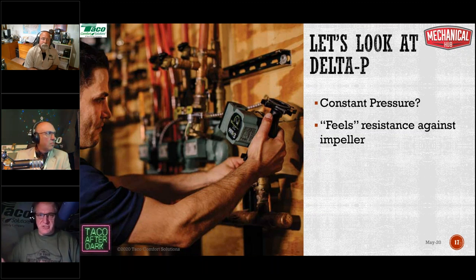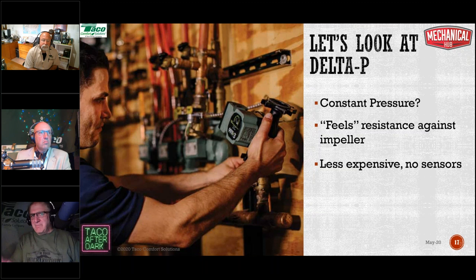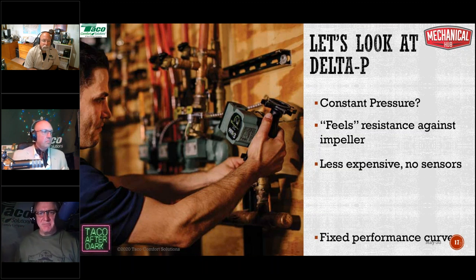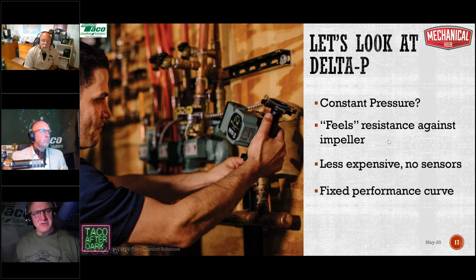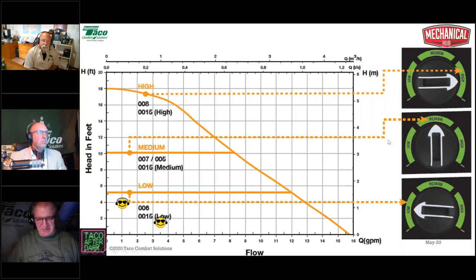Another zone closes, more resistance, and we slow down again. A zone opens, less resistance, something's changed, so I must go faster to maintain my 10 feet of head constant pressure differential. That's how it works under constant pressure, which is the most common mode that you'll use it in. A lot of people like delta P because it's less expensive than delta T and there are no sensors involved, internally or externally. In a little delta P pump like that, there are no sensors internally and nothing external that you have to set up. So it's simple, easy and less expensive, but the performance curve is fixed. And here's an example of that.